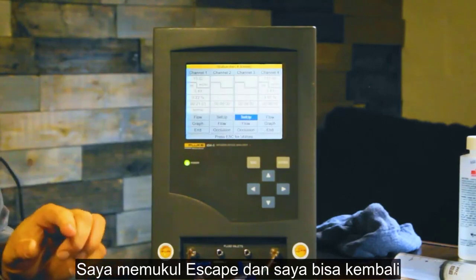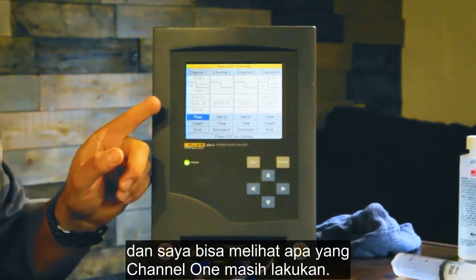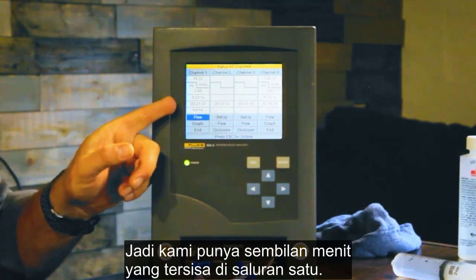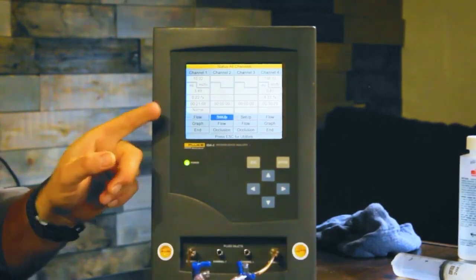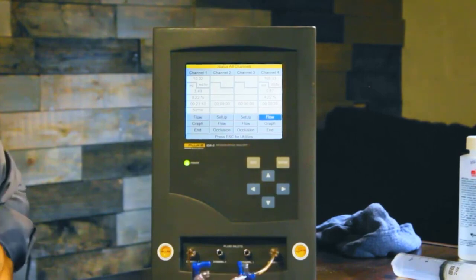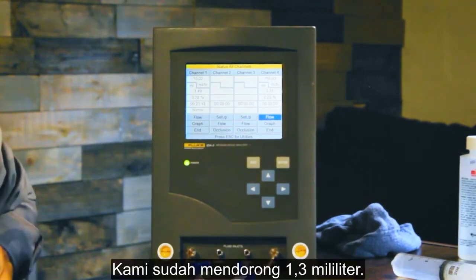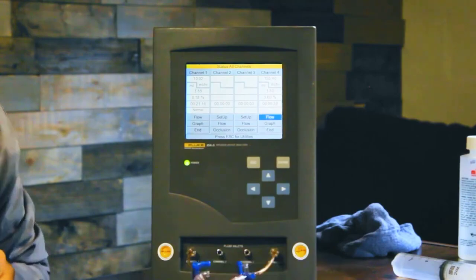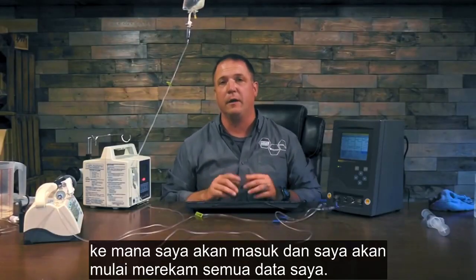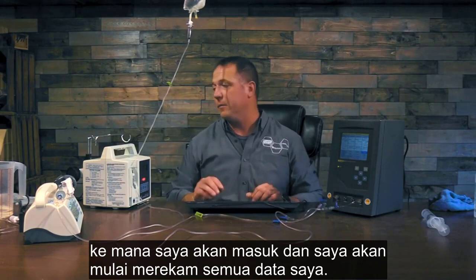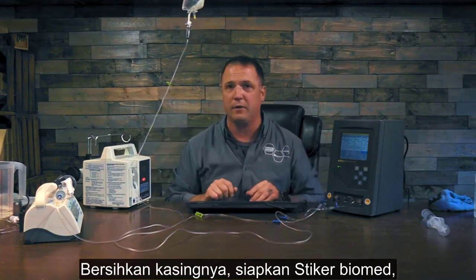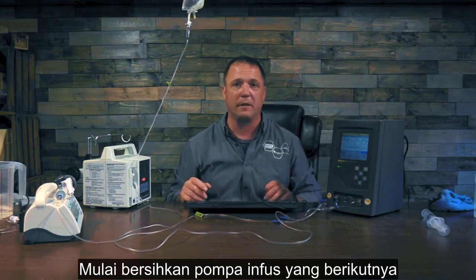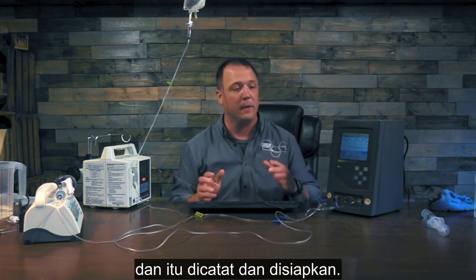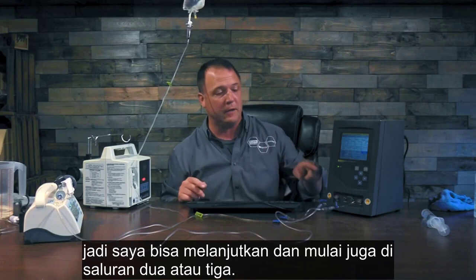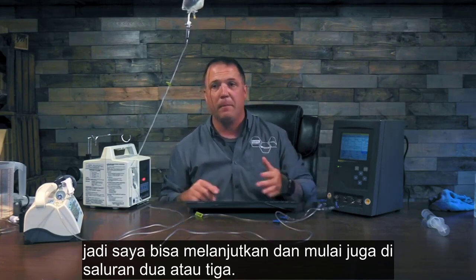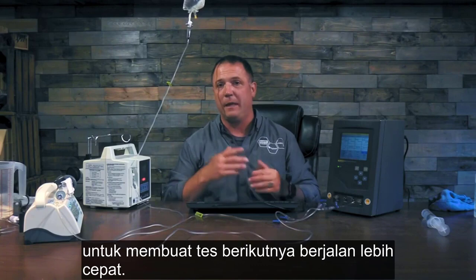I hit escape and I can go back and I can see what channel 1 is still doing. So we have 9 minutes left on channel 1. All right? Channel 4, we've already pushed 1.3 milliliters. Okay, so this is the point in time where I'd go ahead and start recording my data. Clean the cases, get my Biomed sticker ready, start getting my next infusion pump cleaned and logged and set up. Again, we have 4 channels here, so I could go ahead and get channel 2 or 3 going. But there's lots of things I can be doing to make the next test go faster.